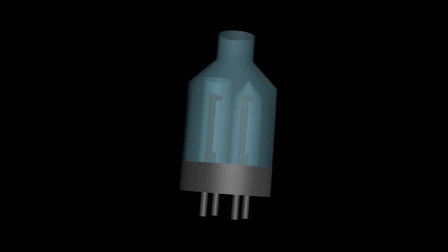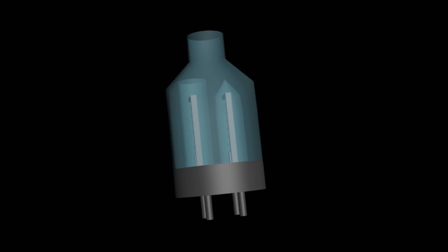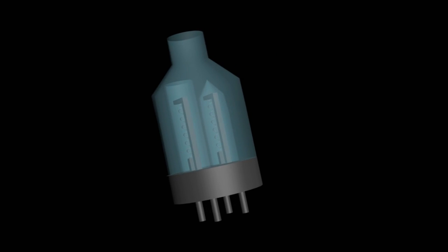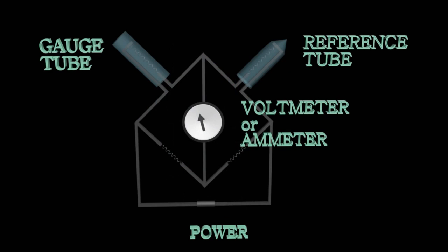One of the filaments is placed in the gauge tube and it is exposed to the environment where the pressure is measured. The other filament, however, is placed in a sealed reference tube filled with gas at constant pressure.